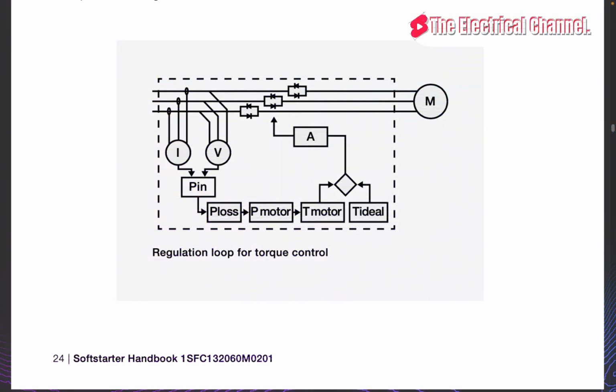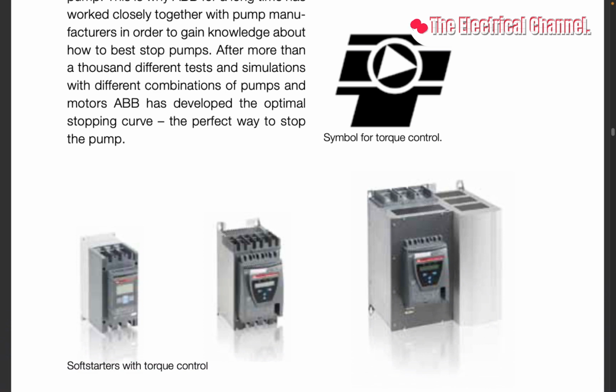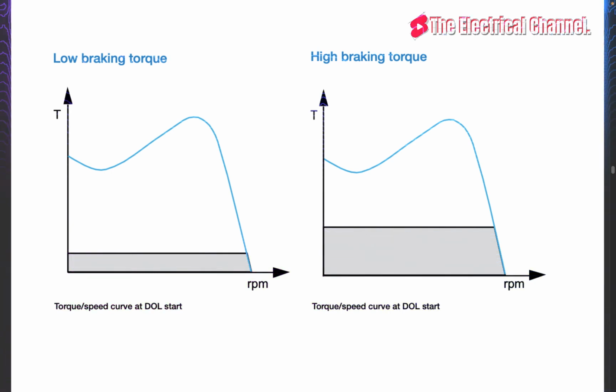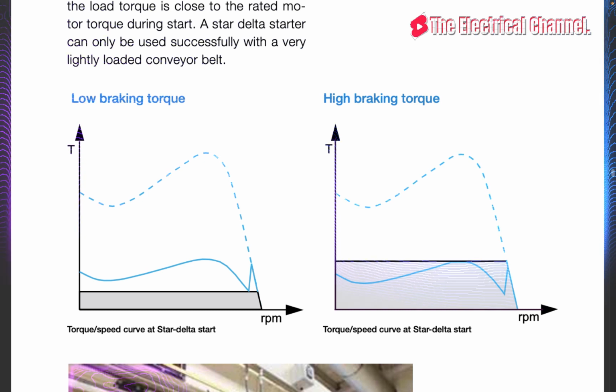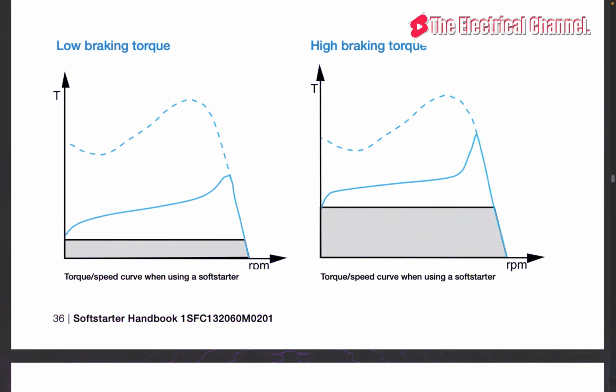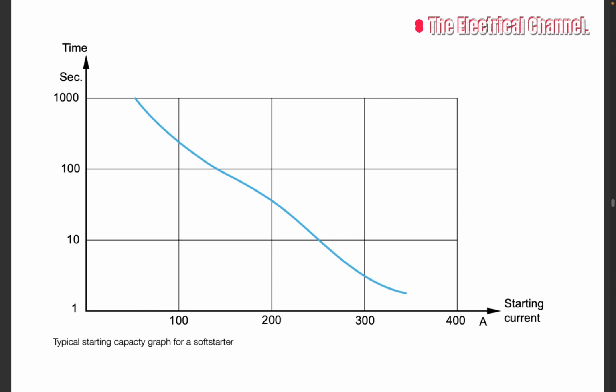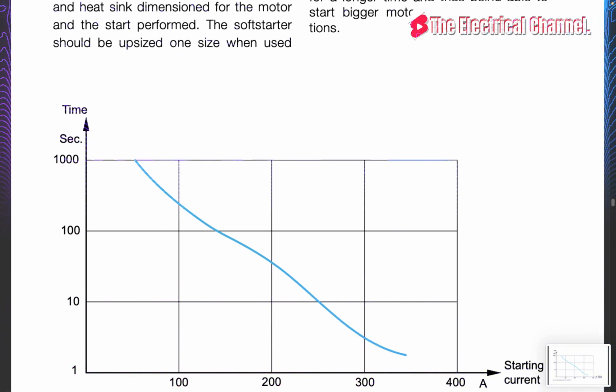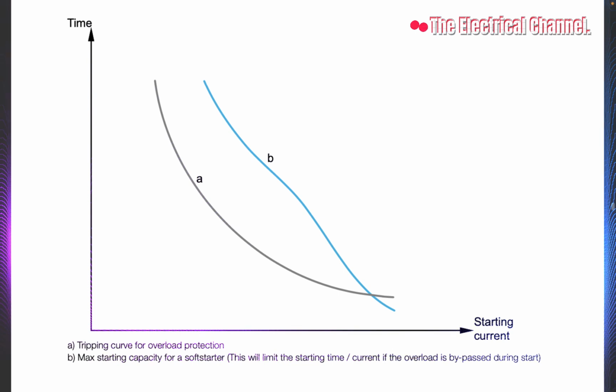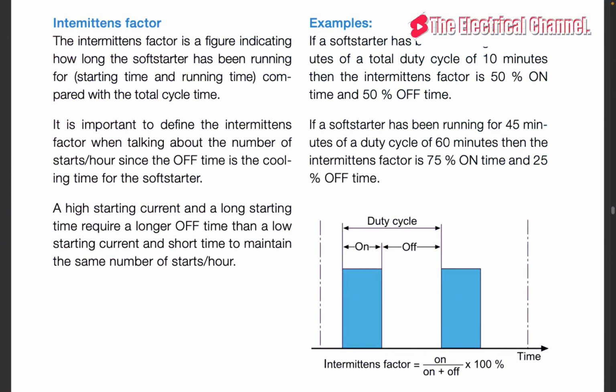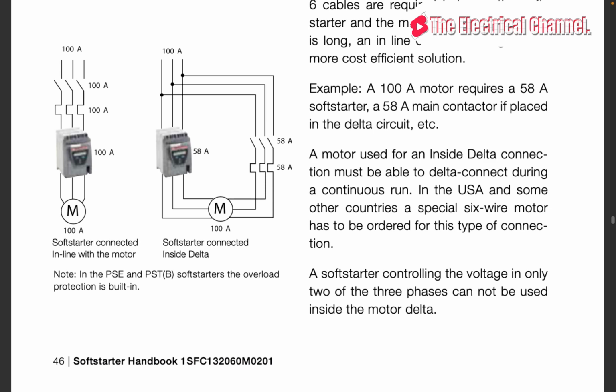One of the benefits with this starting method is the possibility to adjust the torque to the exact needs. Whether the application is loaded or not, using a soft starter will reduce the starting current and thereby avoid voltage drops in the network. It will also reduce the starting torque and mechanical stress on the equipment, resulting in reduced need for service and maintenance. Just as for a drive, the soft starter can perform a soft stop, eliminating water hammering and pressure surges in pumping systems and avoiding damage to fragile material on conveyor belts.